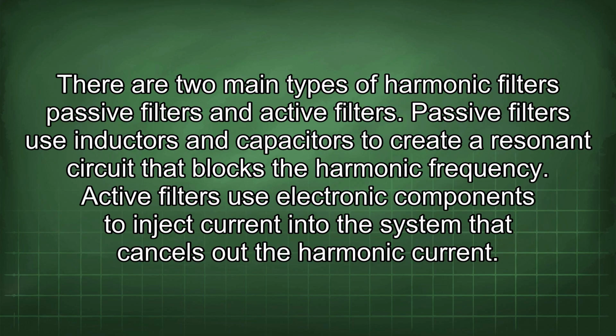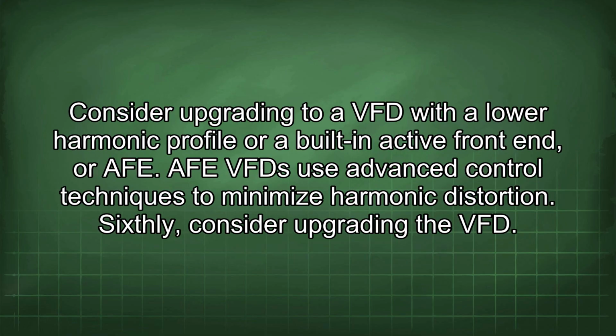There are two main types of harmonic filters: passive filters and active filters. Passive filters use inductors and capacitors to create a resonant circuit that blocks the harmonic frequency. Active filters use electronic components to inject current into the system that cancels out the harmonic current. Consider upgrading to a VFD with a lower harmonic profile or a built-in active front end, or AFE. AFE VFDs use advanced control techniques to minimize harmonic distortion.